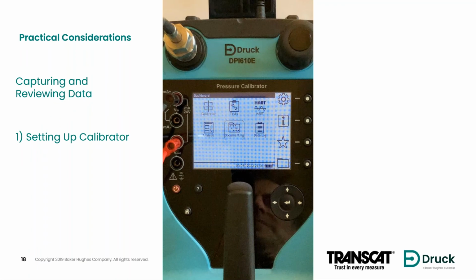There are capabilities within many portable pressure calibrators to be able to capture data. So you can do this on a number of levels. It wasn't my intention to go through a long and detailed discussion about documenting calibrators, but I wanted to cover the documenting feature because it can be very convenient in troubleshooting, because you can capture the data at the site where you're troubleshooting, and then you can go back and review it to identify where an issue may have occurred to help you in your countermeasure or correction of that fault.